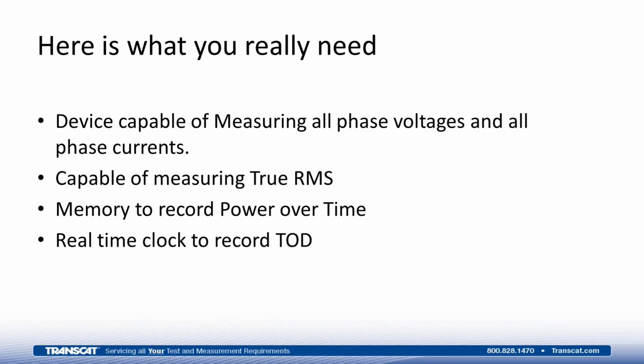If I'm sampling that waveform, which is occurring 60 times a second, by the way, fast enough so that I'm picking up all the points on the waveform, the product is called a true RMS meter. The reason we specify that is that there are other devices in the industry that do not look quickly enough, miss some of the things going on during the fluctuation of the voltages or currents, and express misleading values. Those devices would be known as averaging products, or products that don't identify themselves as true RMS. So if you're doing this type of measurement, it's critical that you use an instrument capable of reading quickly enough to pick up the actual values of voltage and current.